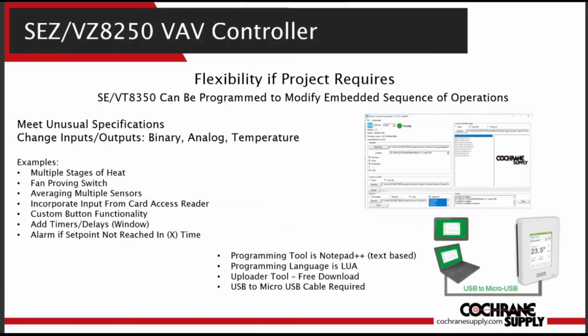You can add a stage of heating or add a fan proving switch. You can average multiple sensors to control a larger space. You could incorporate an input from a card reader in a hospitality installation. You could create a custom button on the display so when the user pushes it, special functions occur. We've got a library of over 2,000 programs that are modifications we've worked on over the last couple years. So please ask your Cochrane representative if you're looking for functionality above and beyond what comes out of the box.